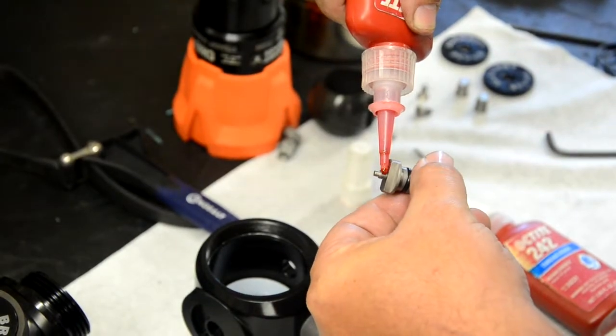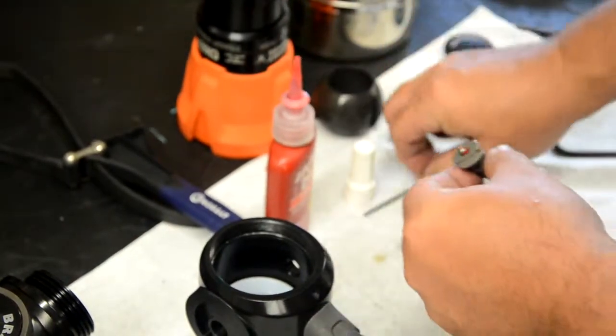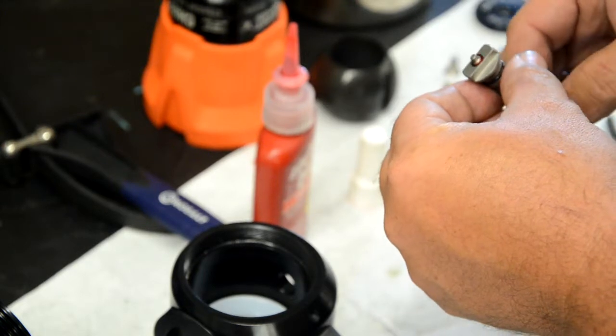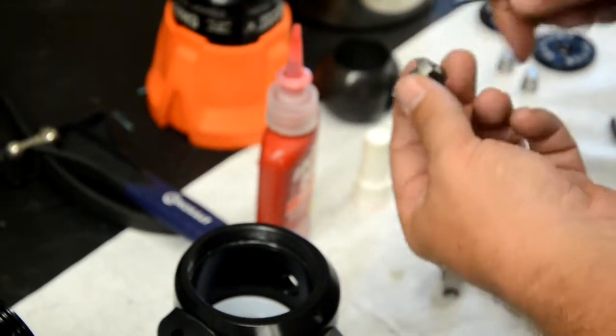After applying the Loctite, back the dog point set screw back into the actuator shaft until it's flush. Be sure to apply Dow Corning number 7 silicone grease to the o-rings on the actuator shafts as well.